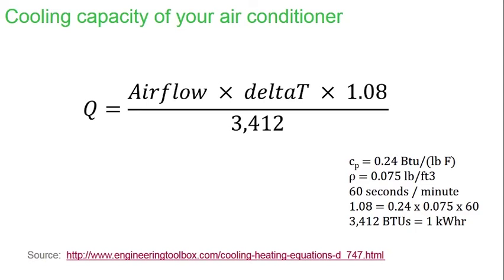The lesson here is that you should not waste fan energy by having your CFM — the airflow — too high, and you shouldn't have it so low that you starve your IT equipment. What I want to summarize is that your delta T across your cooling unit needs to be similar to the average delta T across your IT equipment. Understanding why that is will help you reduce your fan energy and still effectively cool your IT.